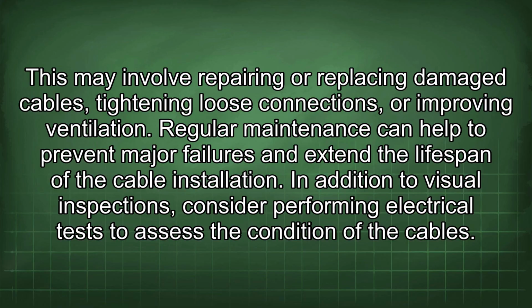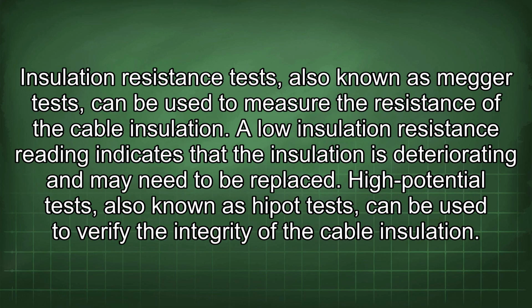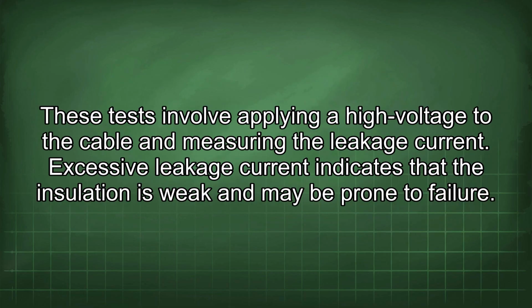In addition to visual inspections, consider performing electrical tests to assess the condition of the cables. Insulation resistance tests, also known as Megger tests, can be used to measure the resistance of the cable insulation. A low insulation resistance reading indicates that the insulation is deteriorating and may need to be replaced. High potential tests, also known as hipot tests, can be used to verify the integrity of the cable insulation. These tests involve applying a high voltage to the cable and measuring the leakage current. Excessive leakage current indicates that the insulation is weak and may be prone to failure.